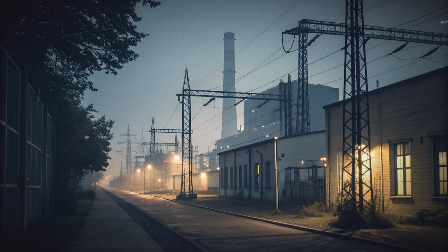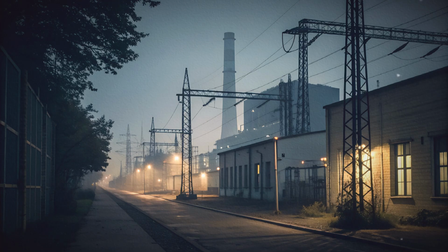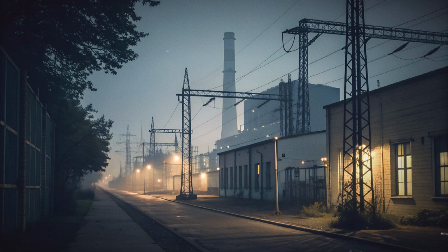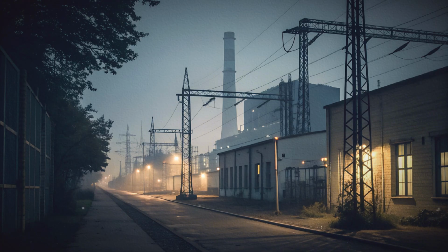Inverter-based resources introduce different dynamics. Solar and wind farms connect to the grid through power electronics. These inverters convert direct current or variable frequency alternating current into the grid frequency. They do not always provide the same inertia effects as synchronous generators. Inertia is the property of rotating masses that slows the rate of change in frequency when system conditions change. To manage this, system operators rely on fast-acting reserves, synthetic inertia provided by some modern inverters, and energy storage systems.